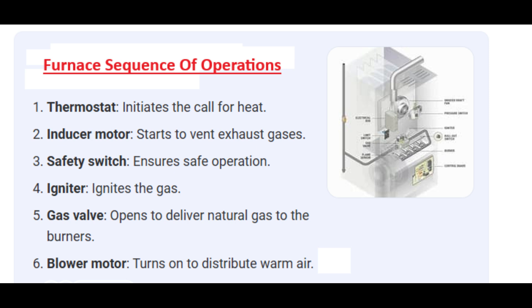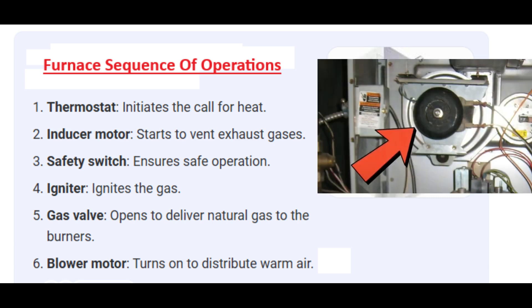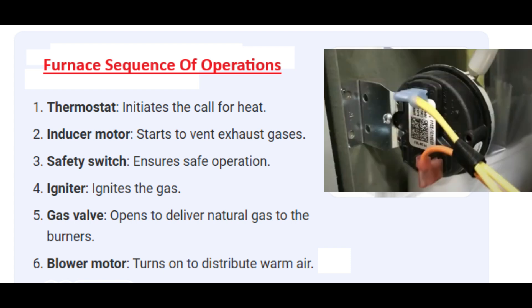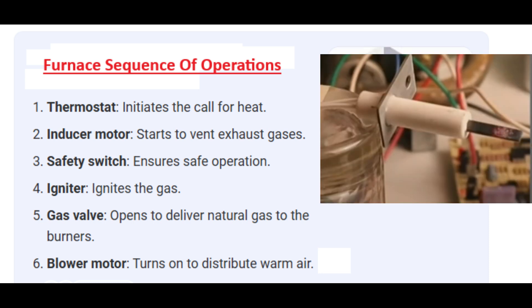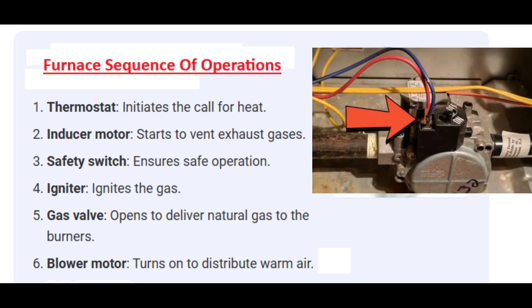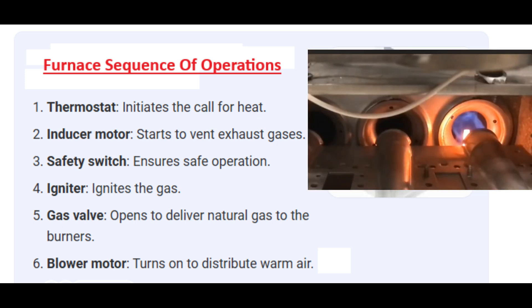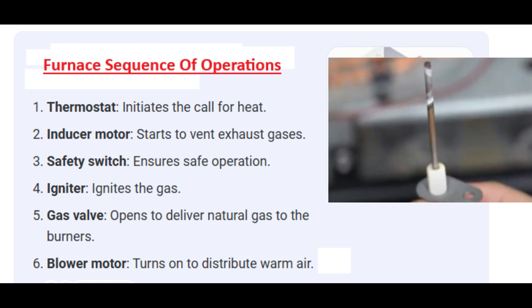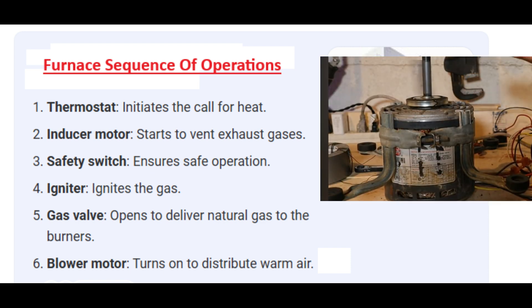For example, on a furnace, the sequence of operations — and we get into more detail on this in other videos — starts with the thermostat initiating a call for heat. The inducer draft motor begins to run, the differential pressure that motor creates pulls in a diaphragm in a safety switch, closing it. Once the control board determines that switch has been closed, it begins to heat up the hot surface igniter until it glows. The control board then sends a signal to activate the solenoid in the gas valve; the gas valve opens and the flame fires up. At that point, the control board uses the flame sensor to verify there is a flame, and after a short delay, the blower motor turns on.